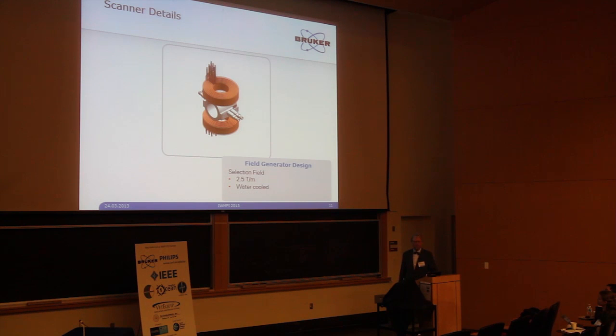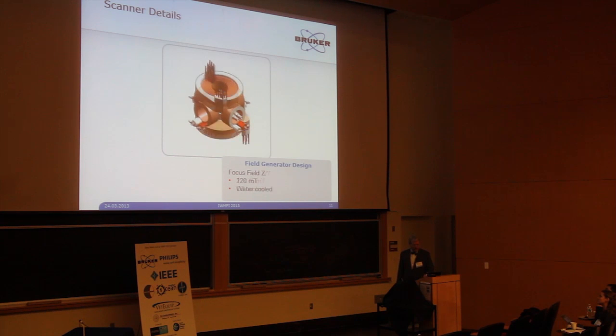Around that is the selection field, a scalable selection field made from copper hollow profiles, water-cooled, up to 2.5 Tesla per meter. Actually, it's run by a 500 amp current, quite a lot actually. Then we have the shift coils in the X-Y direction in the plane, and additional shift coils in the vertical direction, again 500 amps, quite a lot, water-cooled. The whole thing is enclosed in a cubic housing, and you can see it's actually rather compact, 50 by 50 by 50 centimeters, not large.